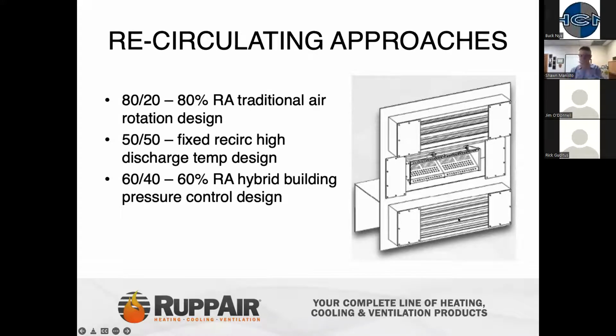So traditional 80-20 units or traditional recirc style systems were referred to as 80-20 units for this reason: 20% constant fresh air and the 80% balance coming in through the top chamber or the bottom chamber. Commonly used in the past, these are more common for balancing or pressurization of building rather than just straight up heating of buildings. But that's kind of where the 80-20 came from. Next, I'm going to talk about 50-50 systems. 50-50 is a term that got picked up as more of a fixed recirc style system.